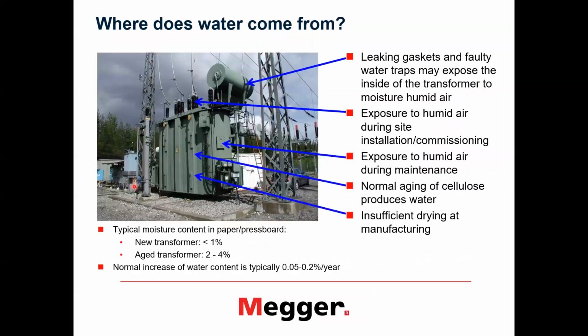So where does the water come from, how does it get into the transformer? Mainly it is due to leaking gaskets, faulty water traps, and open holes where the water can get inside, like regularly when it is raining or there is high humidity in the air. Another reason is when you expose a transformer winding to humid air during installation of bushings or installation of the transformer itself, as well as if you open it during maintenance. So these are factors to be taken into account. And also, even if the transformer is not opened, the normal aging of cellulose will still produce water nevertheless. That is something which cannot be avoided.